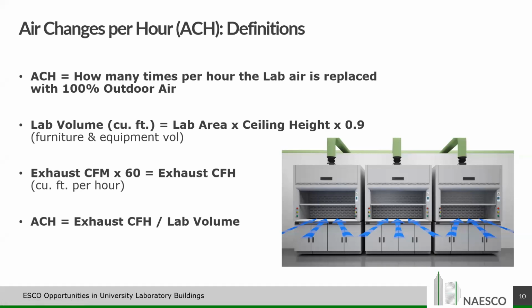Now, over the years there have been some changes, but before we get to that, let's talk about air change per hour definitions. You're going to hear us talk a lot about air changes per hour, and it really is the key to energy savings. It's controlling air changes per hour. The literal definition is how many times within an hour you're going to replace that lab air with 100% outdoor air. To calculate the air change rate, you take your lab volume and use an industry-accepted 0.9 multiplier to account for solid objects in the lab, like furniture and equipment, that are taking up airspace. Then you look at your exhaust CFM, convert it to cubic feet per hour, and divide your exhaust cubic feet per hour by your lab volume. That tells you how many times in an hour you're going to be turning over the air in that room. And that is a key term when it comes to running a safe lab and an energy efficient lab.